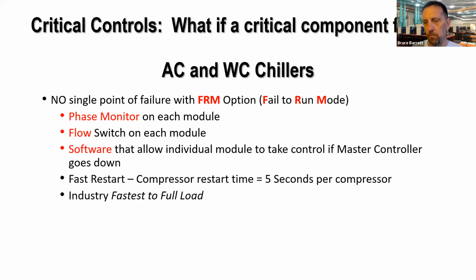Critical controls. We do comfort cooling. We absolutely do a lot of critical cooling. Data centers where they are constantly looking for redundancy and backup if a component fails. And just as our air-cooled we did last week, we offer this fail-to-run mode component to our water-cooled modular chillers. We want to have no single point of failure. So we've added a flow switch to every module. We've added a phase monitor to every module.